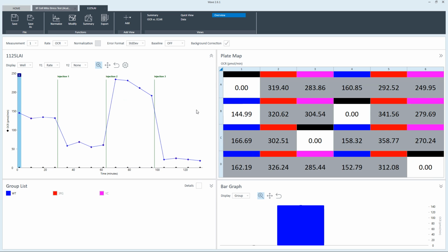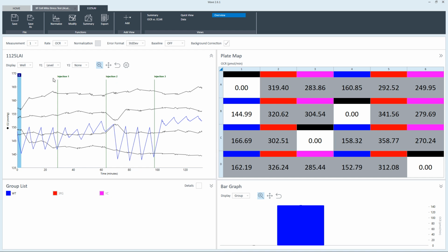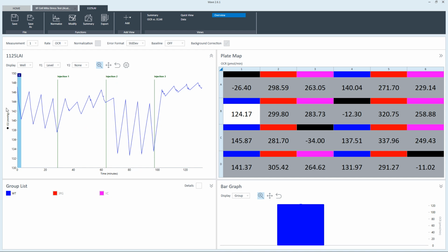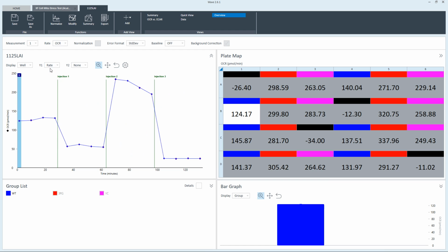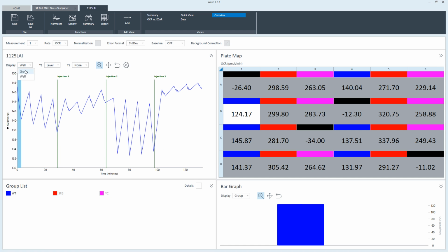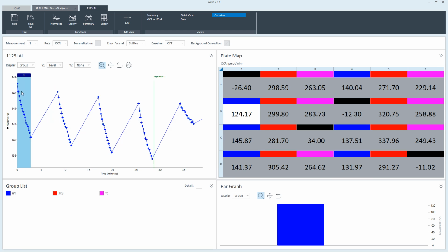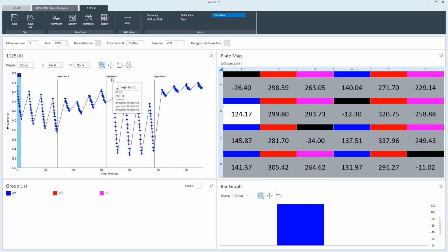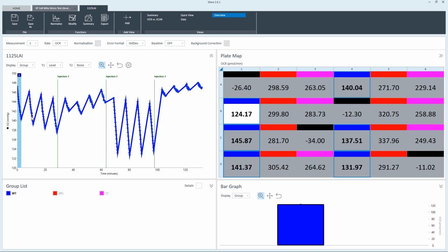And now we just want to measure one thing, which is OCR, and it means rate. As we change the rate to level, we will get the oxygen level. Before, it was OCR, and the unit is picomole per minute, but actually it is calculated from the oxygen level change. From the oxygen level change, you can see it is measure, mix, wait, measure, mix, wait, measure, just like that. So we need to make sure of just one thing: every time the instrument did mix and measure, the oxygen level gets a similar state. So it is acceptable. It is very stable.